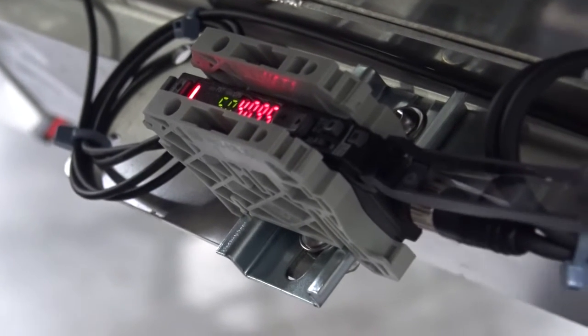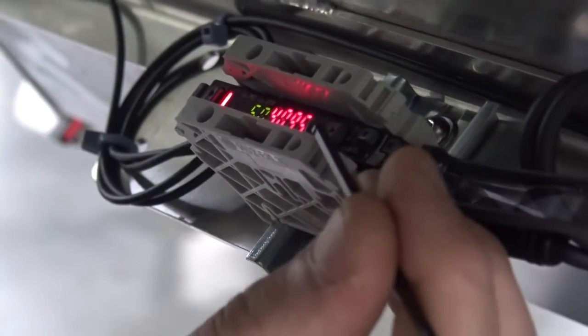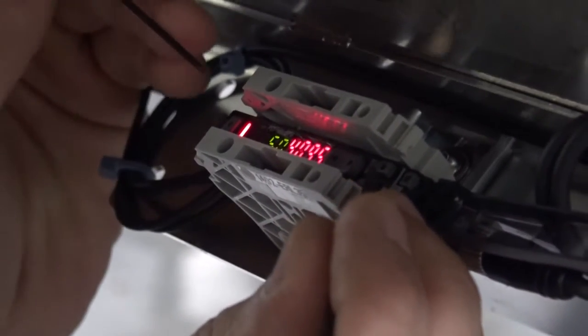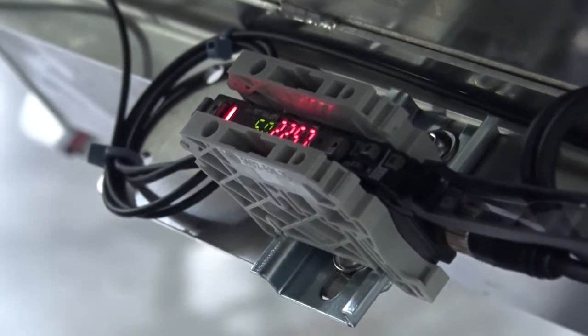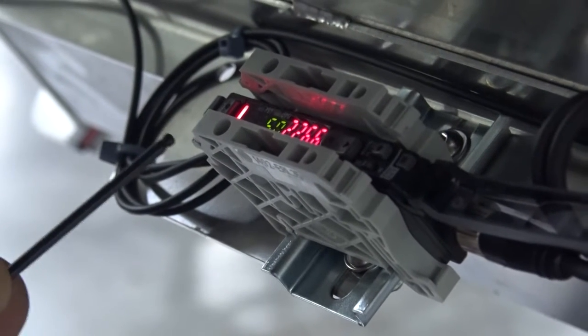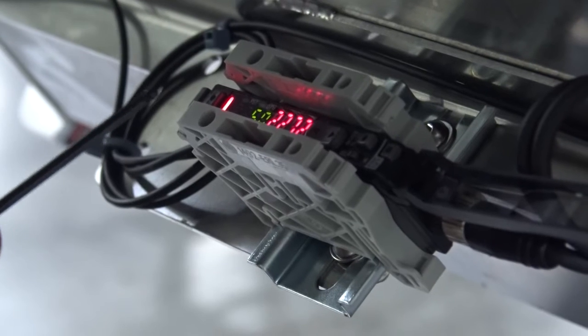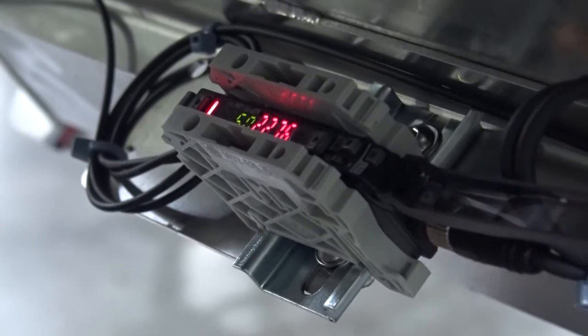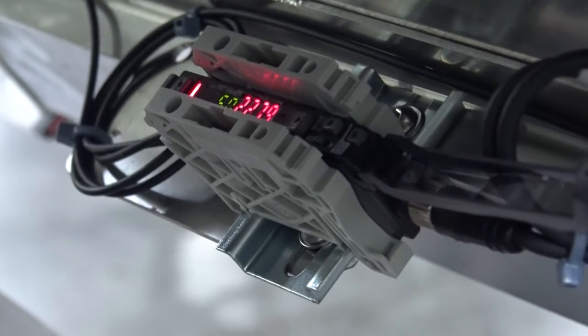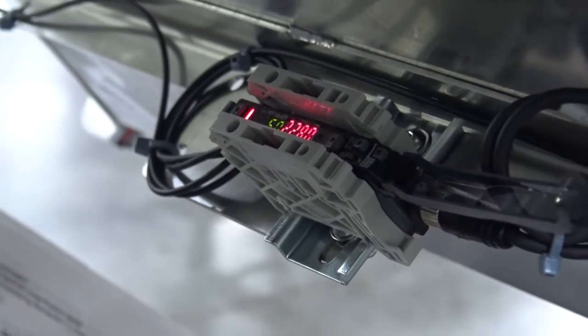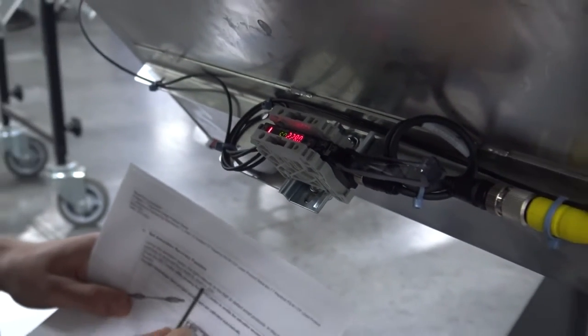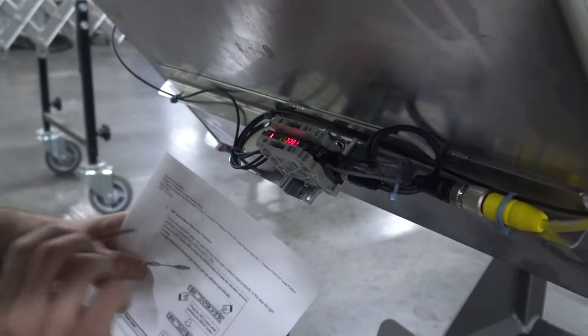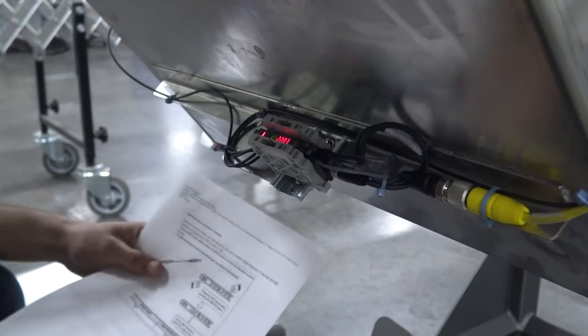So to do that, we're going to press the set button while pressing the mode button, and that'll enable the saturation mode we want. So again, I'm pressing the mode button and I hit set. Okay, now my units, you'll see they went from over 4,000, now they're at about 2,300. And that falls in line with the procedure saying that we're going to go from about 4,100 to above 2,000 plus or minus 350 units. So we're on the higher side, but we're still within the threshold. So now we're in the lower saturation mode. We found that to be best practice for this application.